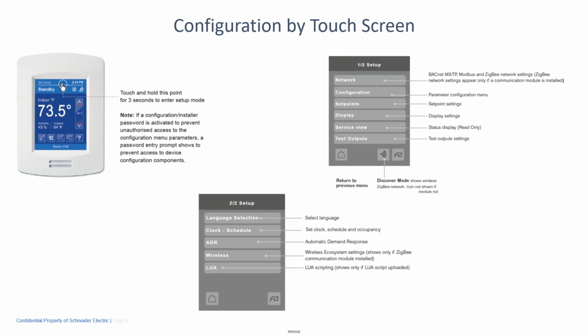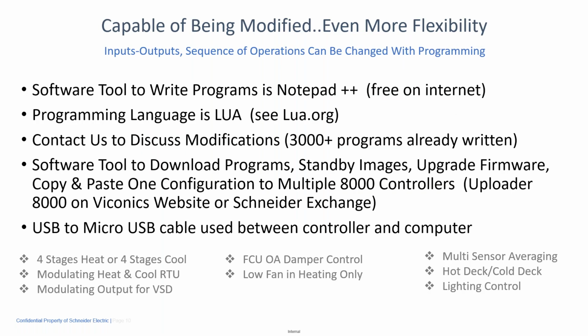So these controllers by themselves have a sequence of operations. You have no need to add any programming to them. But if you want, you can go through and alter what the inputs are, alter what the outputs are, change the sequence of operations, or add timers, do whatever it is that comes to mind. All you're kind of stuck with is the 7 inputs and 9 outputs. You can't do any more than that, right?